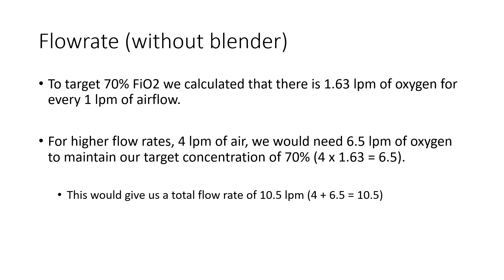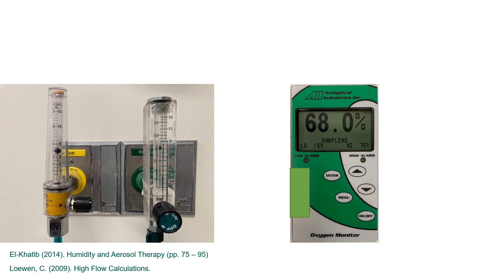So we multiply that by 4, and we get a total flow rate of 10.5 liters: 4 liters air, 6.5 liters of oxygen, and we verify it again, and we get 70% again. So if you don't have this fancy equipment, you can still give precise FiO2 deliveries, but it's important you humidify that gas. And if you have an analyzer, you can just put that in line and just get a feel for it. You don't have to do the math, but analyzers can be hard to come by as well.